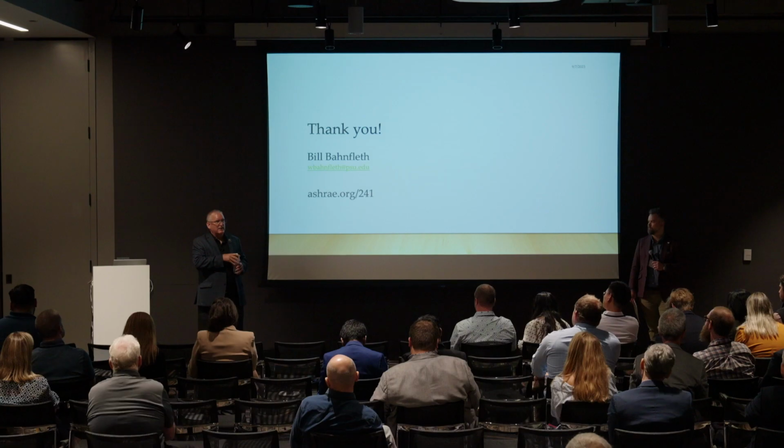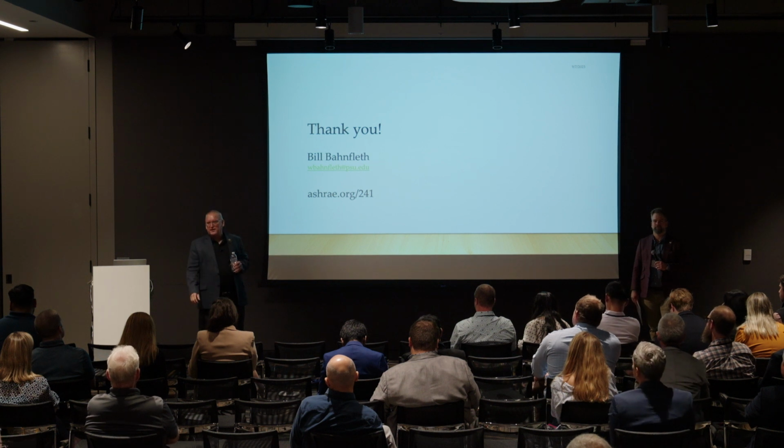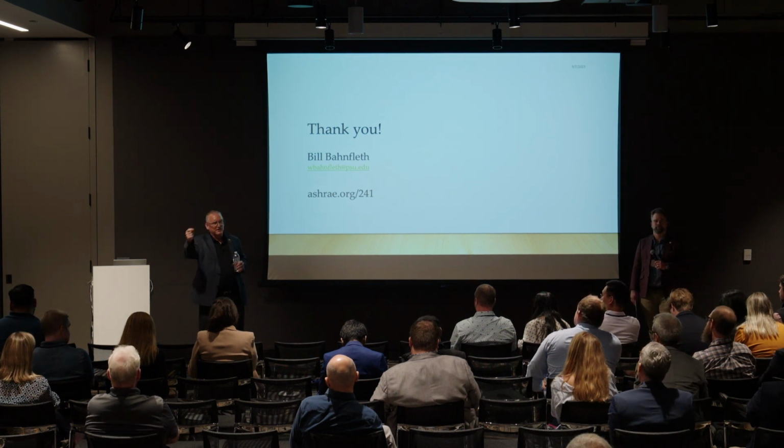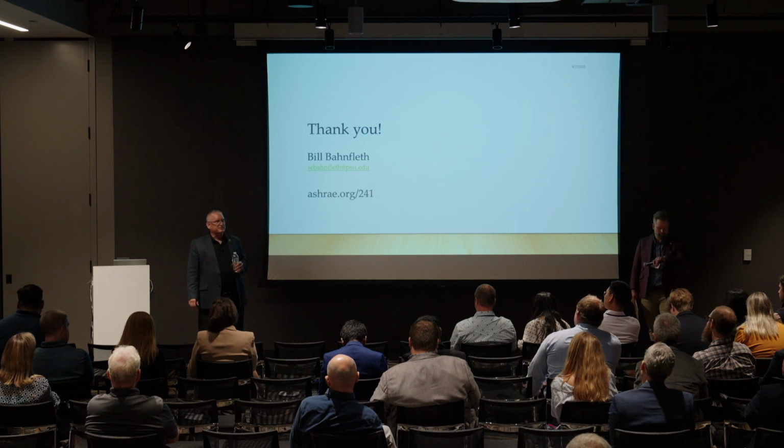IIT has done some of his own testing, but a major manufacturer, I guess this is an ASHRAE meeting, so I can say Trane, tested both bipolar ionization and dry hydrogen peroxide, and issued some really nice reports on it that I think are still available online. That's the kind of testing, and Boeing tested bipolar ionization in aircraft too. So, yes, there is that kind of evidence, but now you've actually got to provide the evidence of complying with these tests to play if you want to meet this standard.